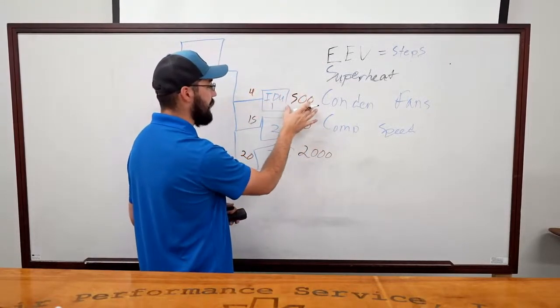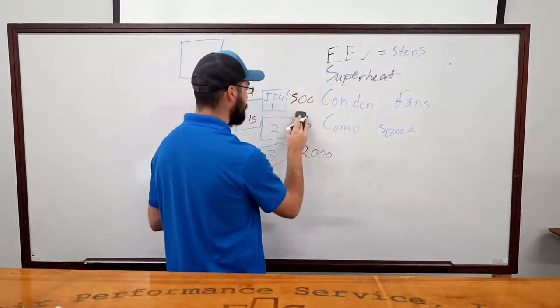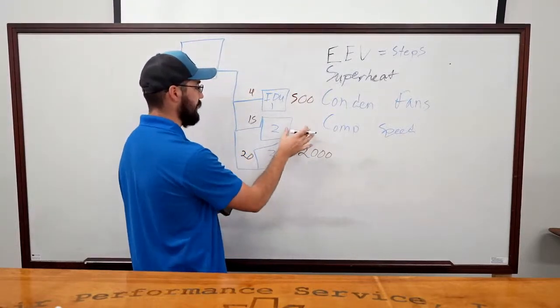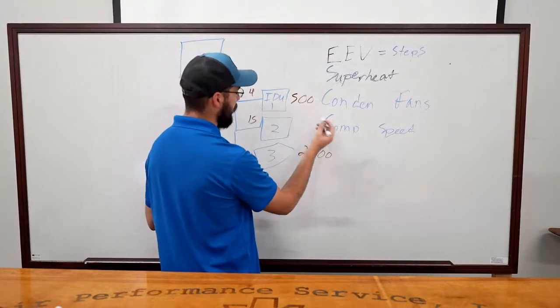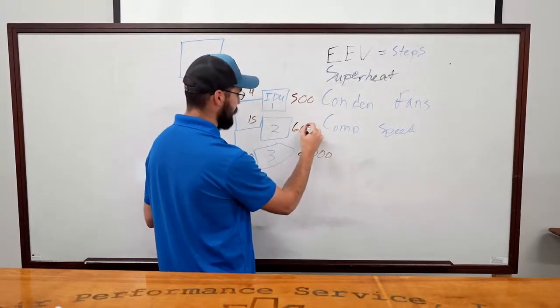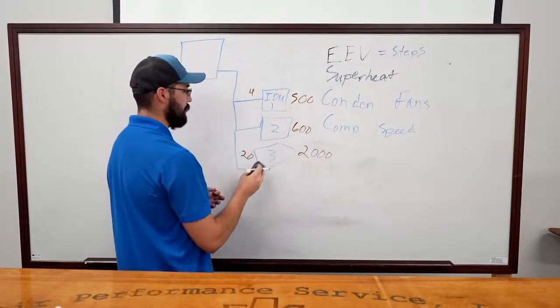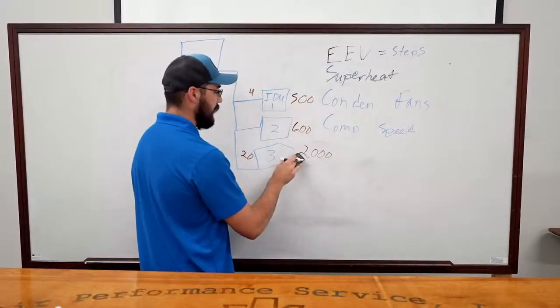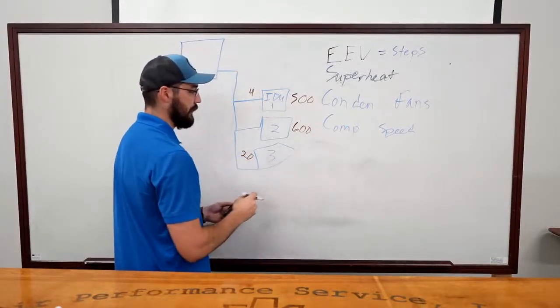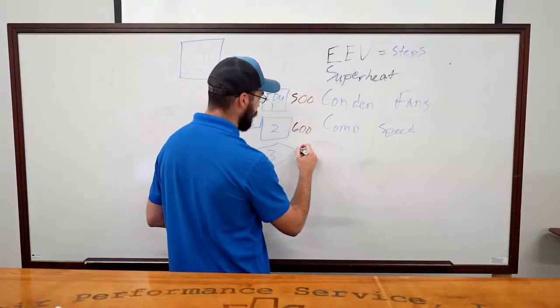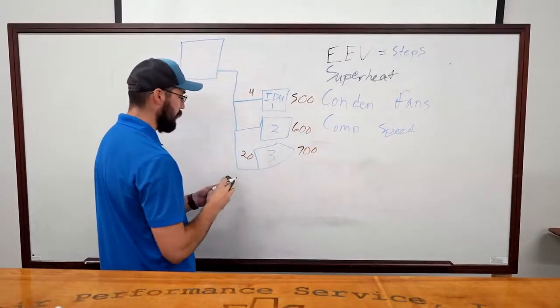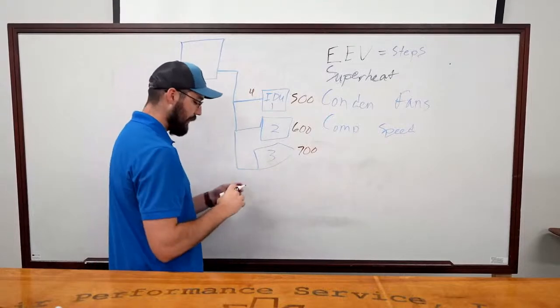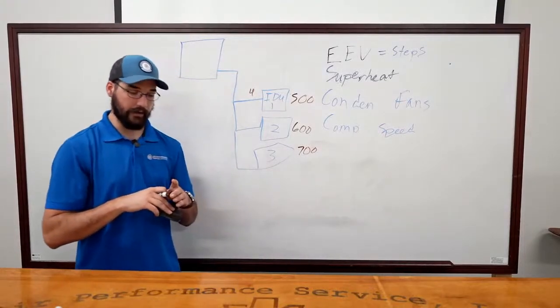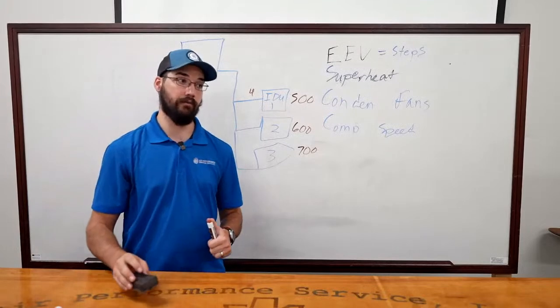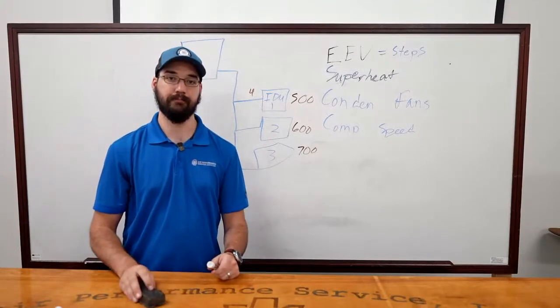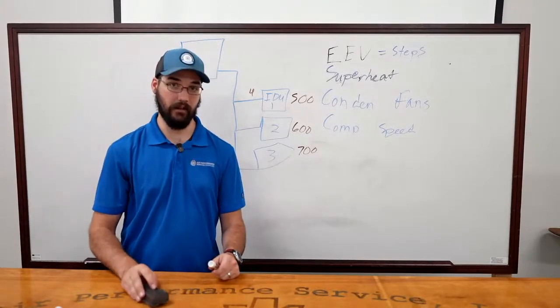And then by the time this one's getting down to 500, you're going to see this second one in the series is able to come down to, let's say, 600, and its superheat drops. And then eventually, the very last one is going to come off of that top end, and we can get it down to, say, 700 or so, depending on load. We can get that superheat down. This is going to take, if you do it correctly, a lot of time. This is not a fast anything.